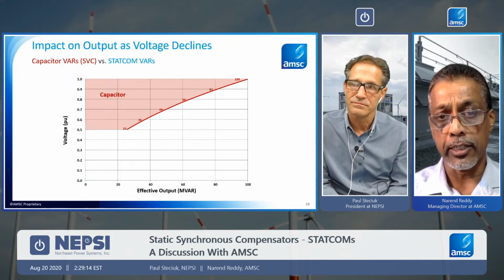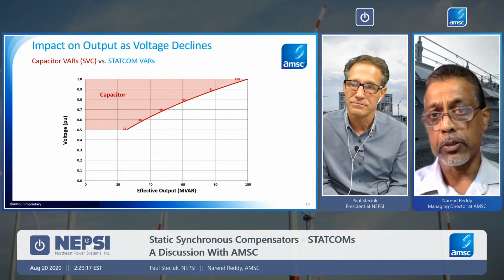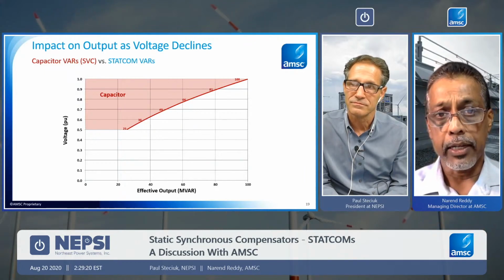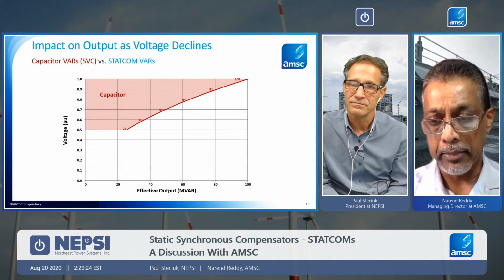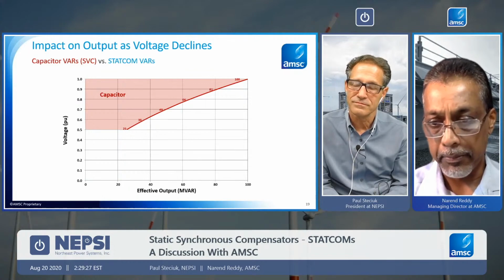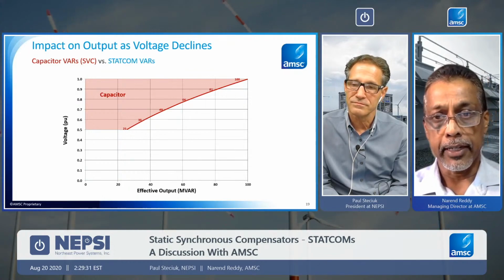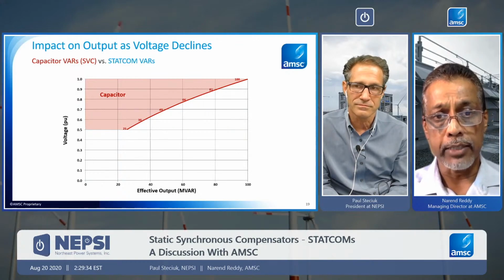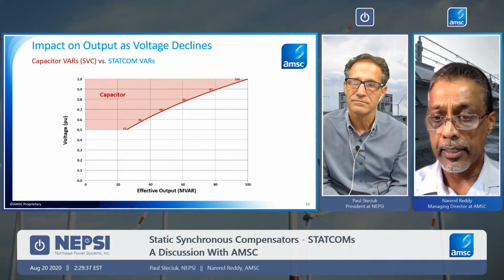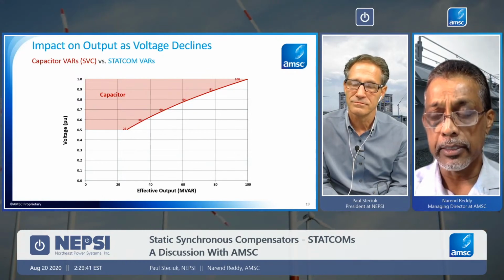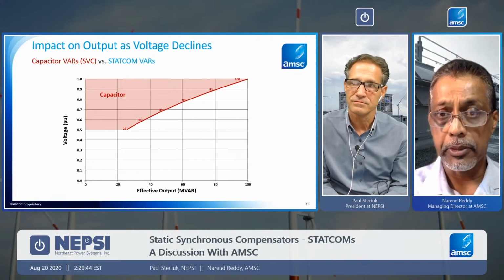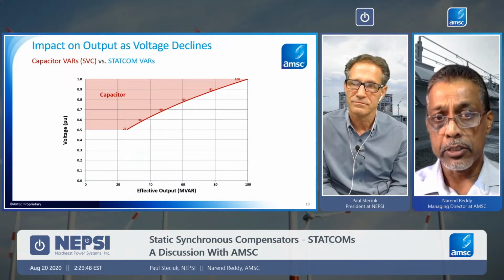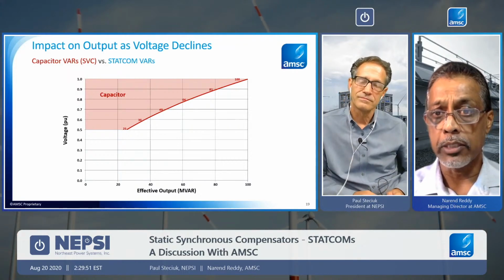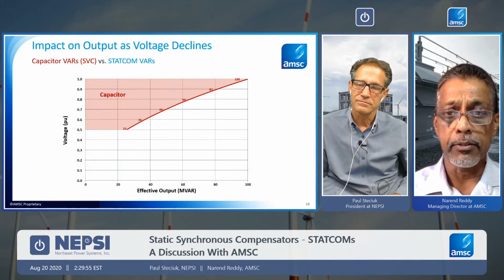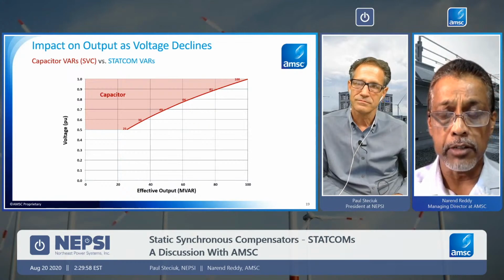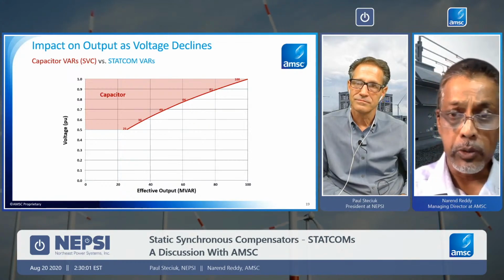Now, this chart I'm showing is voltage versus effective output, and I'm comparing 100 megavar capacitor vars. So think of it as a 100 megavar SVC that's running at full capacitive output. On the Y scale you have the voltage. At 1 per unit, that SVC will give you 100 megavars net output at its terminals. But as the voltage drops to 90%, 80, 70, what you will see here is that the effective output of that SVC, or those capacitive vars, is dropping exponentially by the square of that voltage, right?